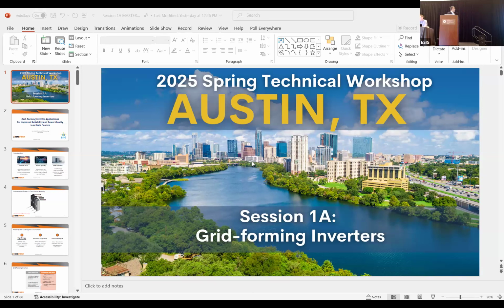The next case study for the integration of grid forming to large grids is the WECC 240-bus system. It is a very large system actually. In the test we did here, we replaced the 5 synchronous generators, 14.9 gigavolt ampere, with 5 battery energy storage grid forming inverters with the same rating and same initial conditions. After that, we create the events. The event we create here is power loss. We disconnect 7 power plants, totally 17.7 gigavolt ampere, in this area.